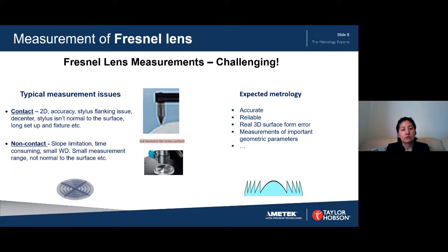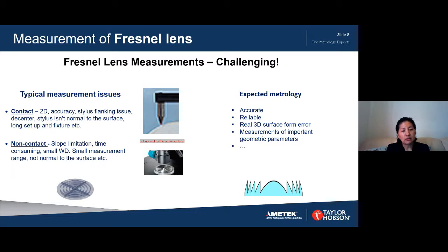Fresnel lens measurement is always a challenging topic for metrologists. So far there is no ideal metrology tool that can cover all the measurement parameters. For example, using a conventional 2D profilometer, it is a 2D measurement and has a stylus flanking issue. The centering of the lens is often critical and it's not easy to ensure the stylus is normal to the surface. Setup can take a long time, even with a custom fixture.